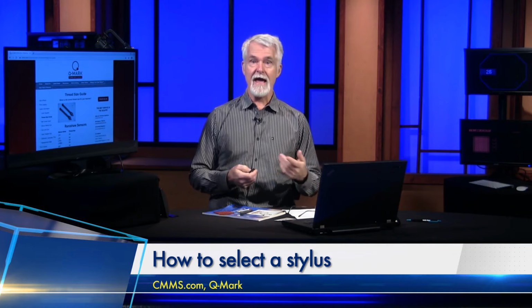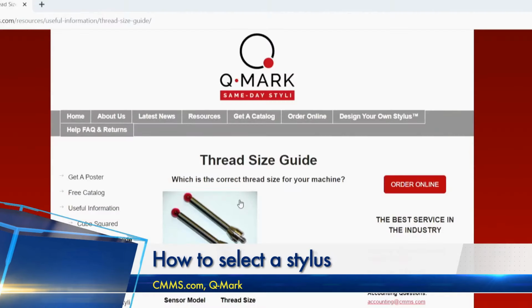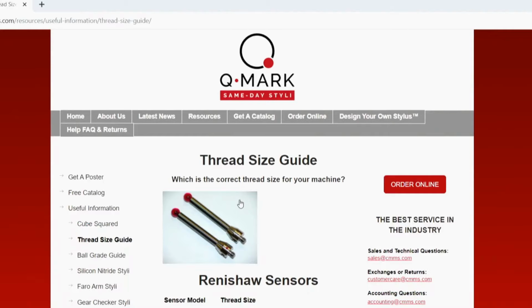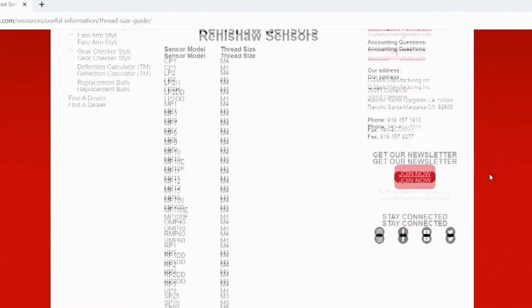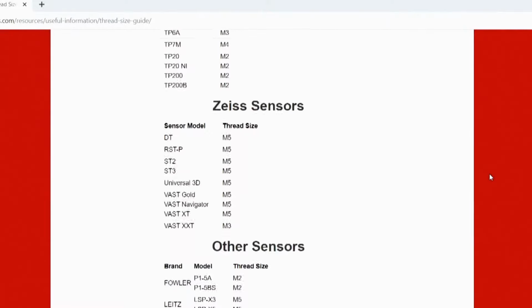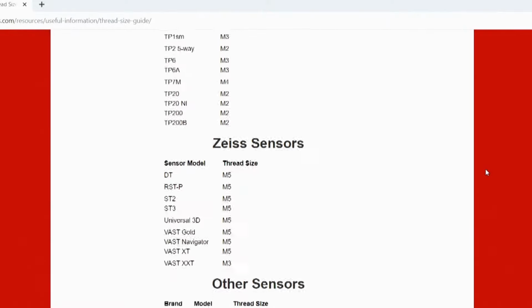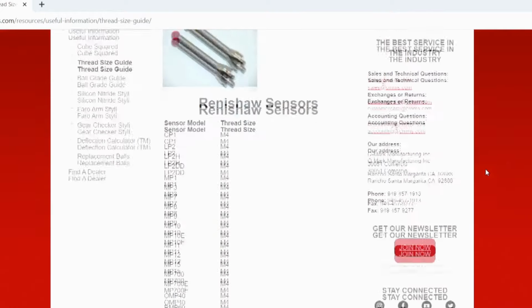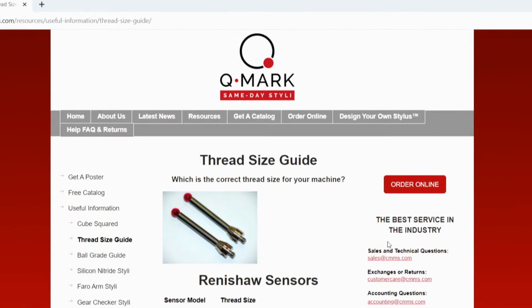And the first thing to do is to find the thread size. So look at the probe head or the sensor on your CMM, see what make or model it is, and then go to QMark's website, cmms.com. That's cmms.com. And I have a link to the page below, but we can see it here. And you can look up the type of probe that you have. We can see there's Renishaw there and Zeiss, and there's some other probes. And you can see if you can find your probe model on there. And if you do, then you have the thread size right there, and that kind of gets you through the first part of this.